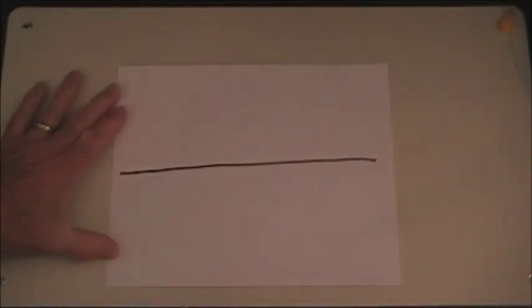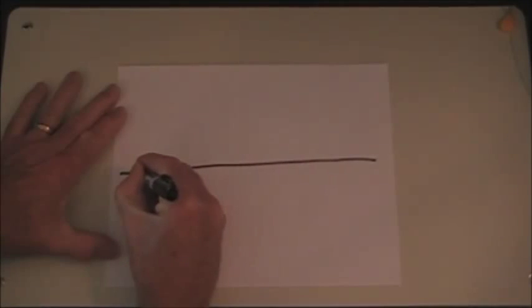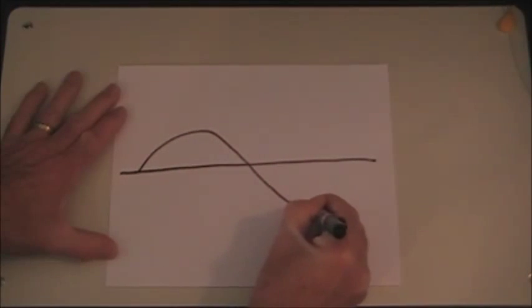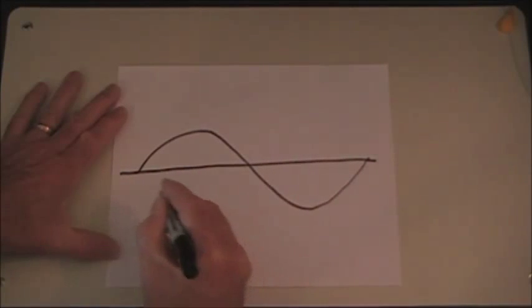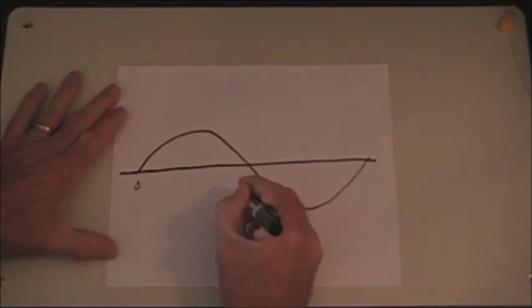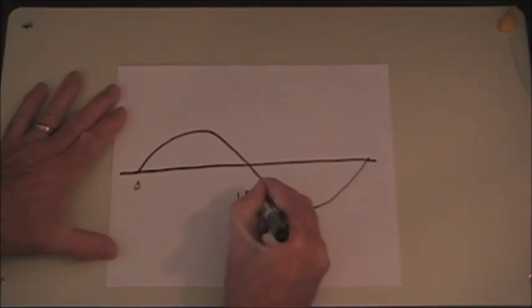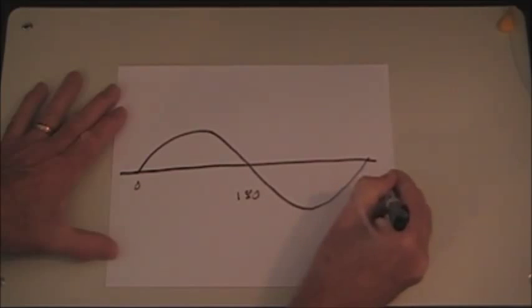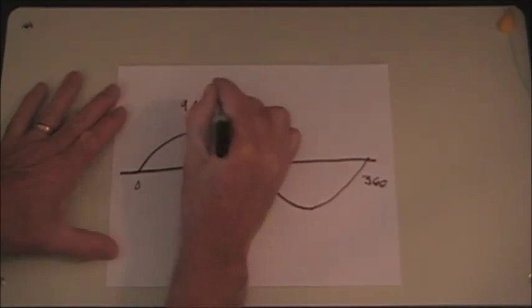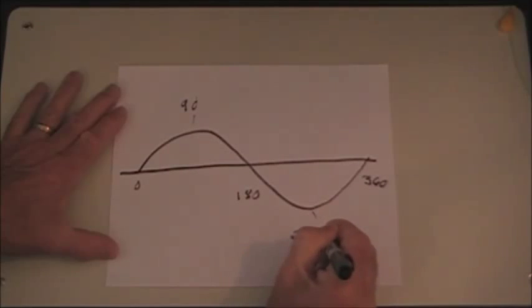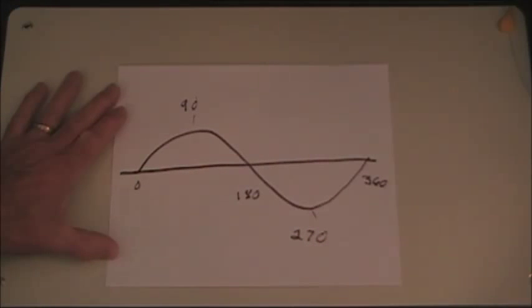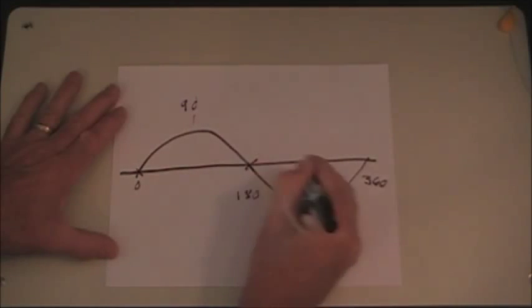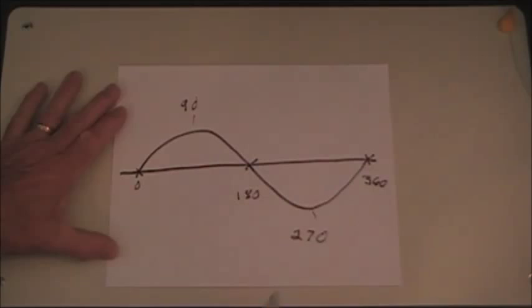If this represents 0 volts, what we're going to do is take a look at one cycle of commercial power. There's the positive half of the cycle, the negative half of the cycle, and we're back to 0. So here we're at 0 degrees, here we're at 180 degrees halfway through the cycle, 360 degrees here. This would be the 90 degree point. This would be the 270 degrees point in the cycle. Now, if an arc is going to occur in a defective component in the commercial power system, it's not going to occur here, or here, or here. Those are all at 0 volts or at ground potential, and that's not going to cause an arc.